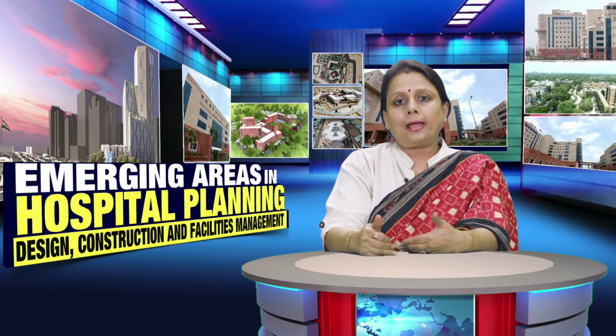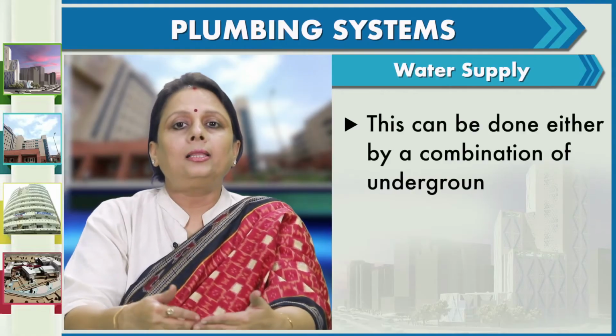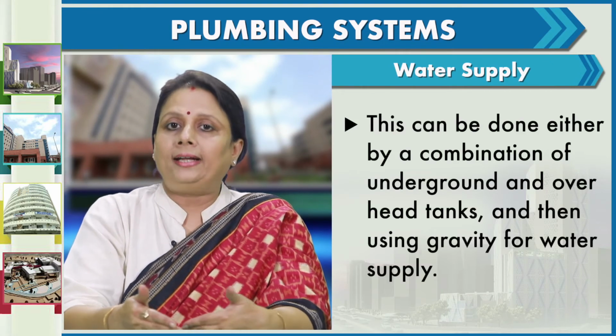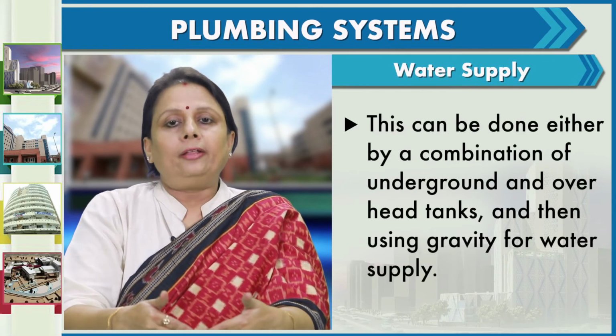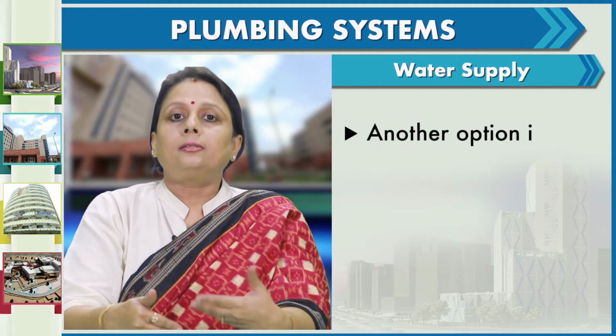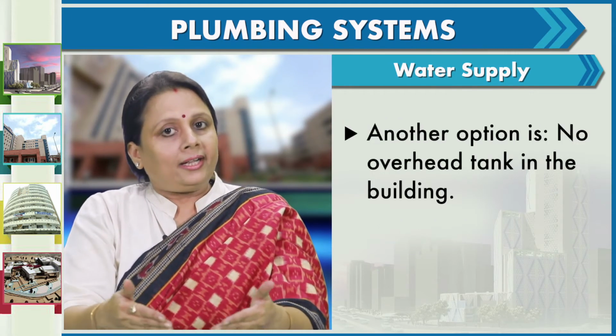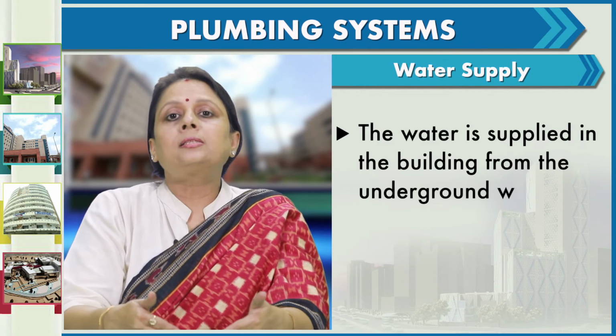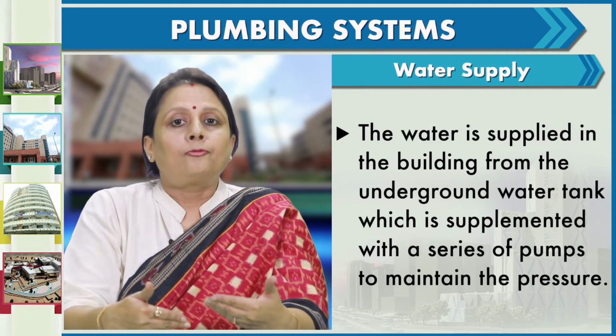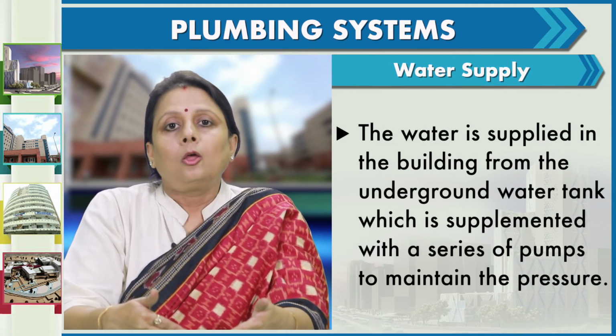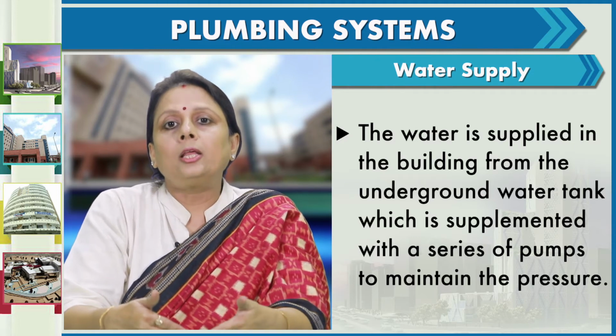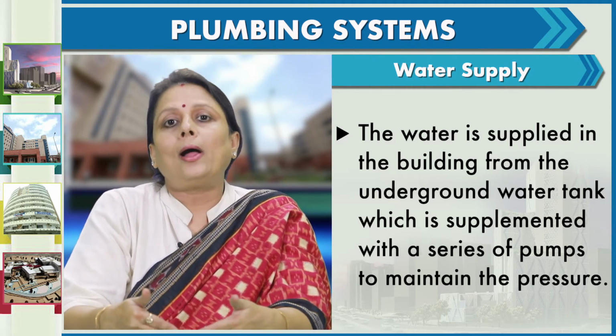As we see in the slide, water supply can be done either by a combination of underground and overhead tanks and then using gravity for water supply. Or another option is that there is no overhead tank. The water is supplied in the building from the underground water tank, which is supplemented with a series of pumps to maintain the required pressure.